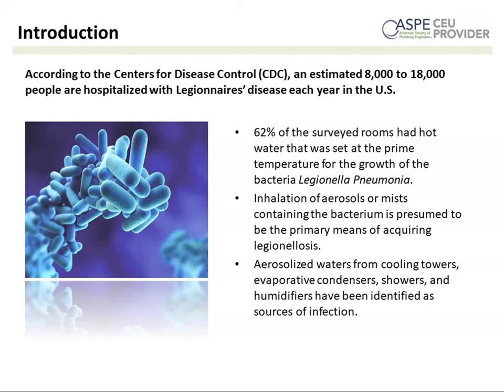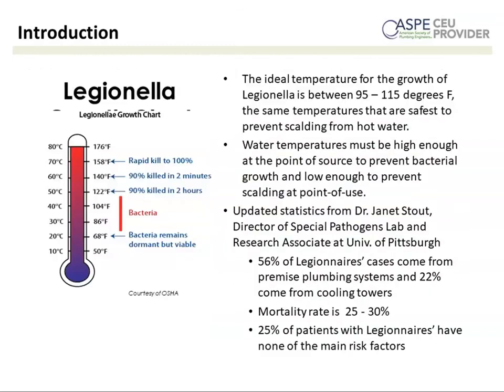Now, Legionella can occur in hot water domestic systems. It can occur from cooling towers. It typically takes place when the bather or the user inhales aerosol or mist containing the bacteria. So again, the ideal temperature growth range for Legionella is between 95 and 115. Water temperatures must be high enough at the point of source to prevent bacteria growth, but again, have to be managed at the point of use to prevent excessive water temperature or scalding.